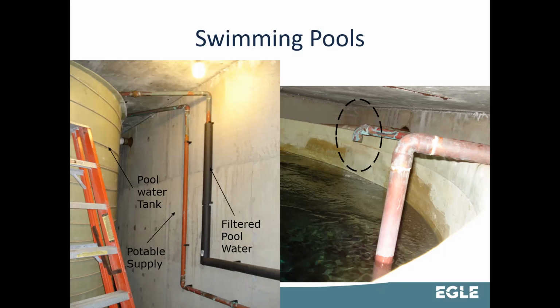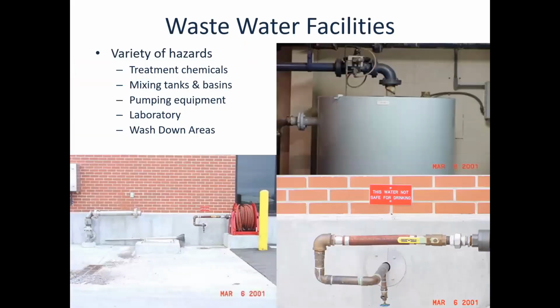So these all are going to need some kind of backflow protection. In this case, you would like to have an air gap. If you can manage air gaps, those are always very simple and a very high order of protection. You just need to make sure that they're not at risk of being a submerged inlet.